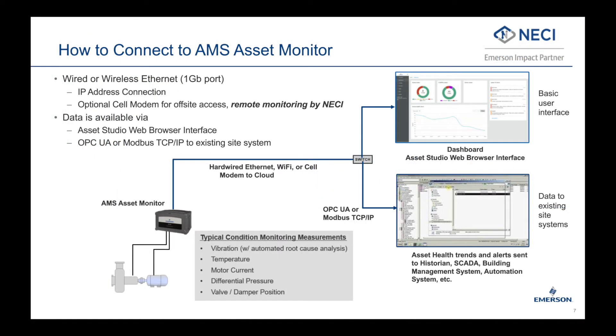To wrap up, let's review how information can be delivered to users to take action. In addition to the dashboard, machine health data can also be brought into any OPC UA or Modbus client for trending and alerting. This could include pretty much any historian, SCADA, building management system, or automation system. The Modbus interface can also be used to bring in process inputs such as speed from a site system. Connection to the AMS Asset Monitor can be made via hardwired Ethernet or Wi-Fi, or via cellular if connection to a site network isn't feasible. NECI can provide integration services to support setting up your desired interface.